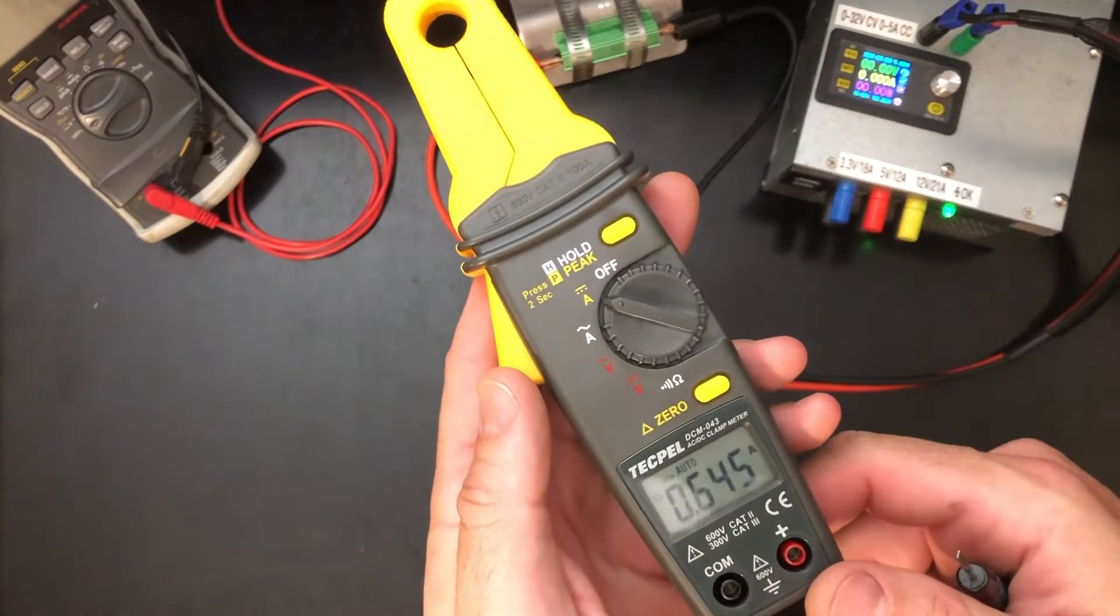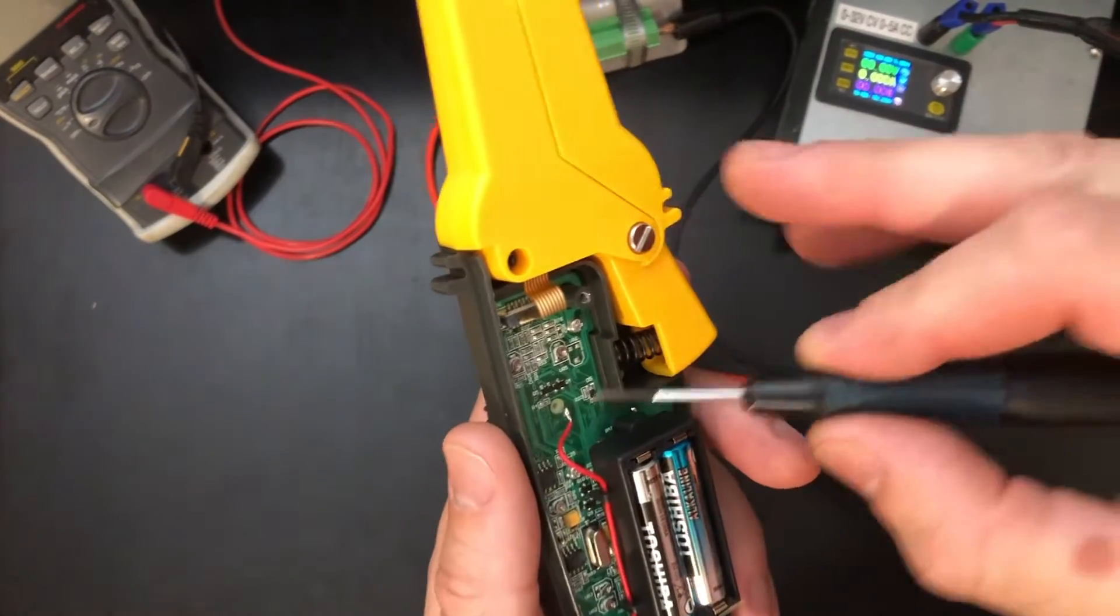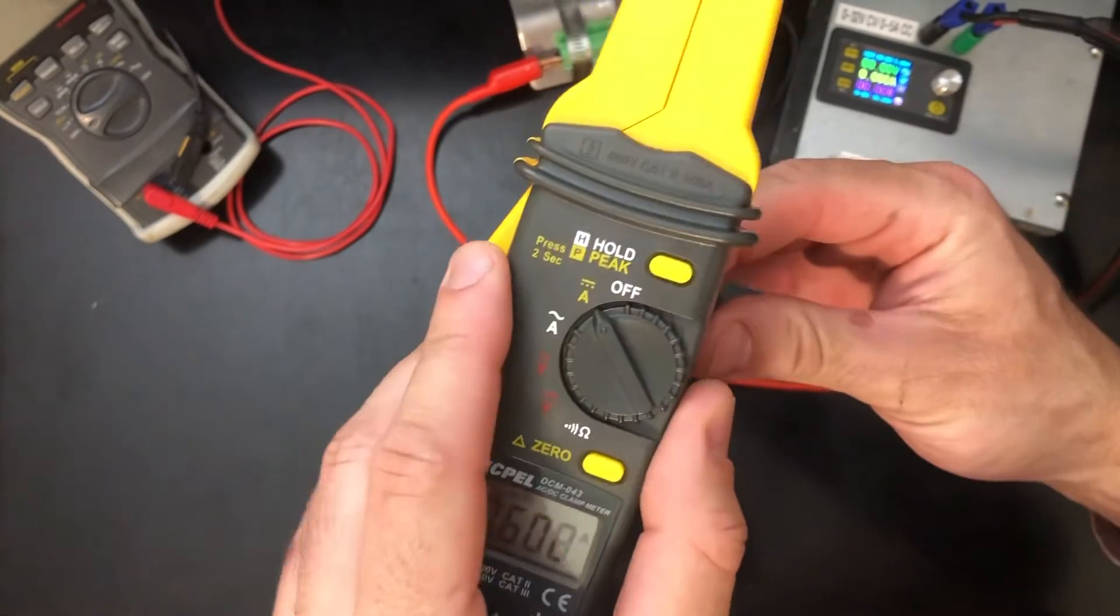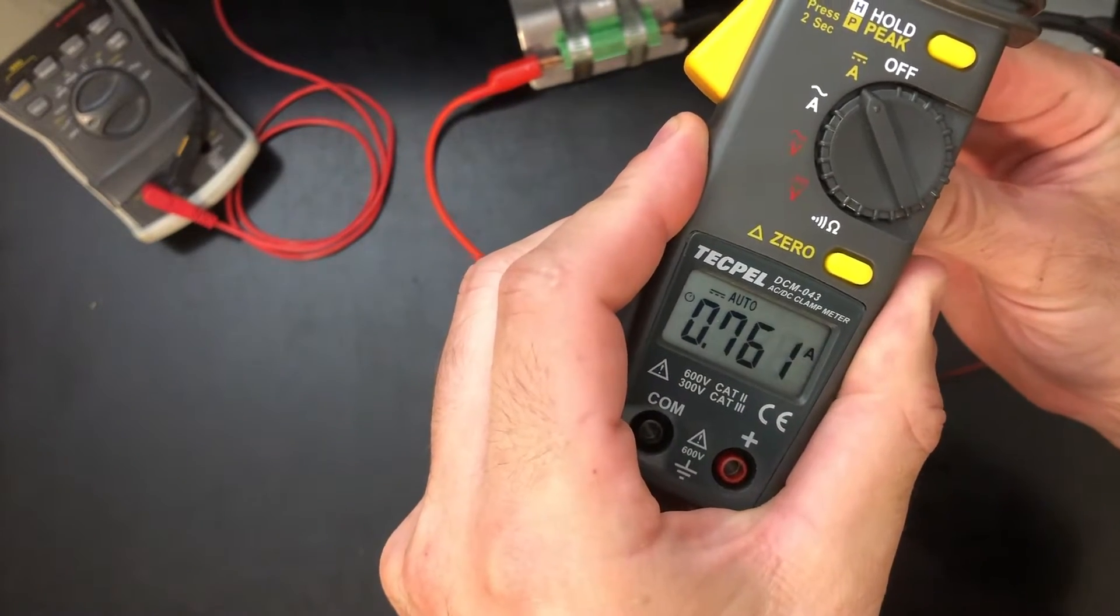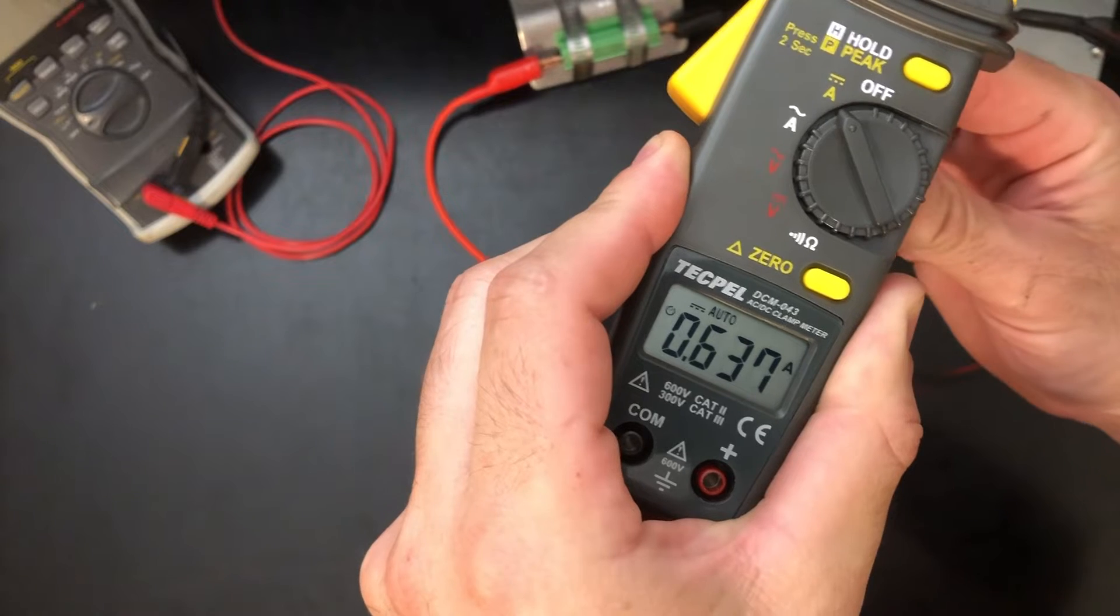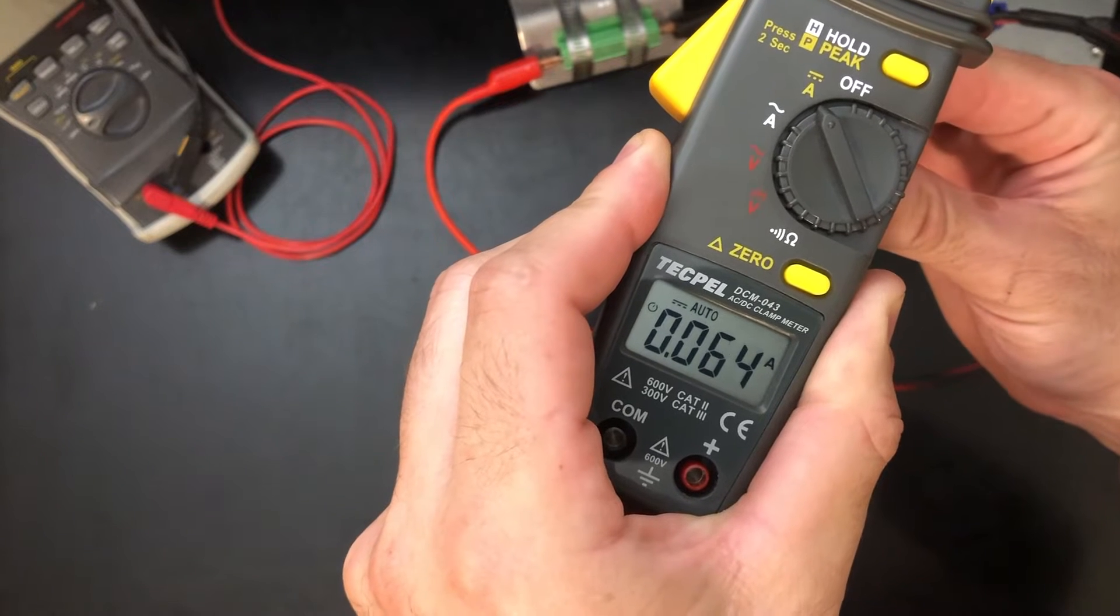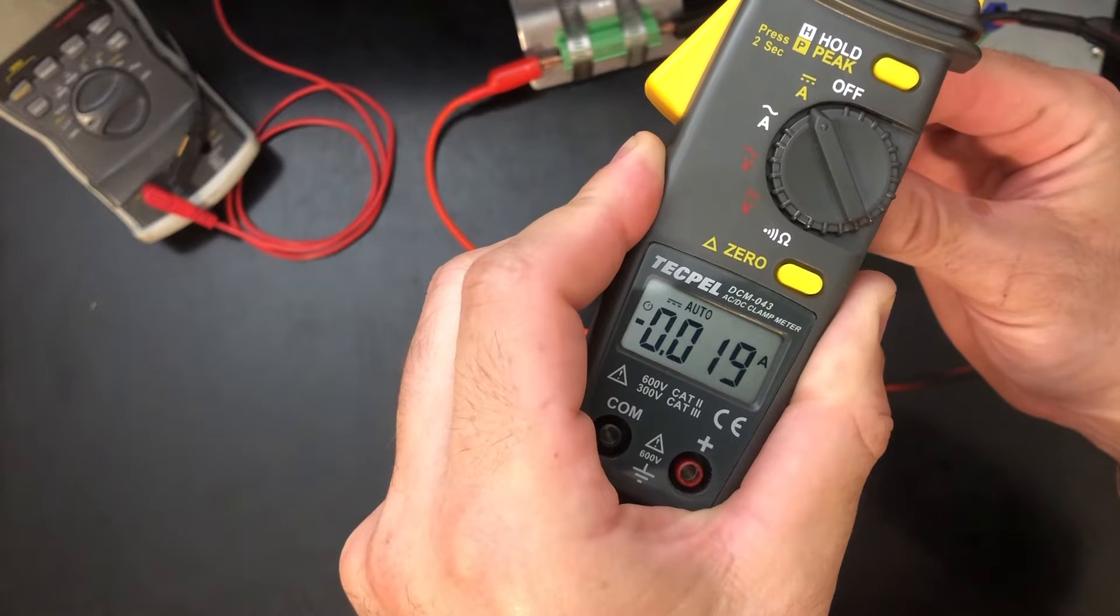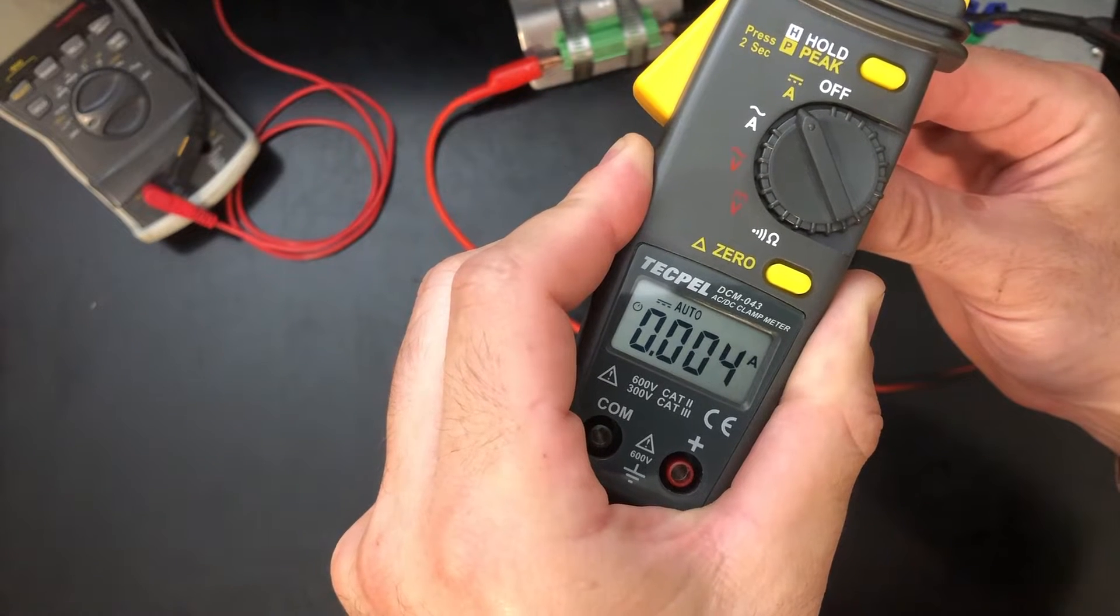So to do that, I'm going to start by adjusting the zero point, and you can see I've still got it in the DC amperage range. I'll turn it over and use my screwdriver to position the blade just inside this left side pot here. While keeping that in place, I'm going to rotate until I can turn that down to zero, and that's actually a clockwise position. I'm rotating very slowly because the update isn't super fast. And as I rotate that clockwise, we're coming up on zero amps. Went past it a little bit, now we're in negative range, so I'm going to bring it back.